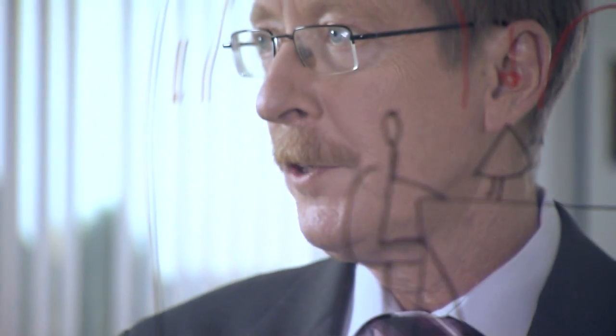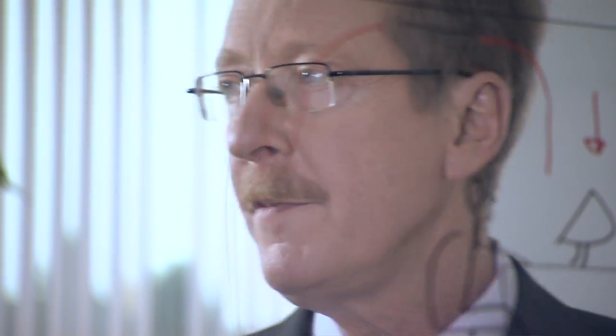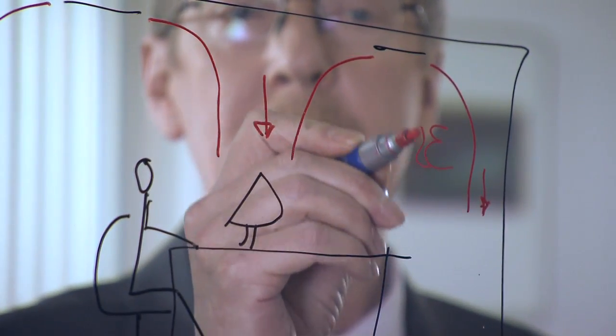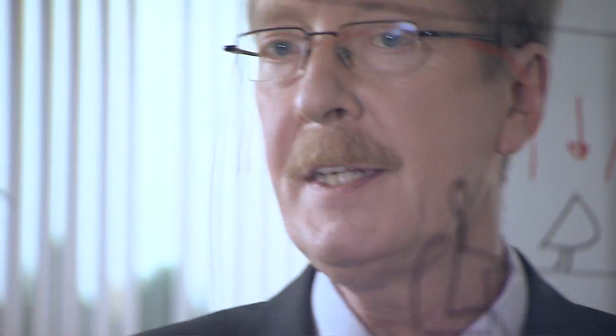The second factor in comfort is the acoustics. Here, the air conditioning system must not generate any noise that can be perceived as an annoyance. The system must also ensure that noise from other rooms does not filter through. This means we have to maintain limiting values of 35 dBA in office areas and 20 dBA in special rooms such as theatres, opera halls and the like.